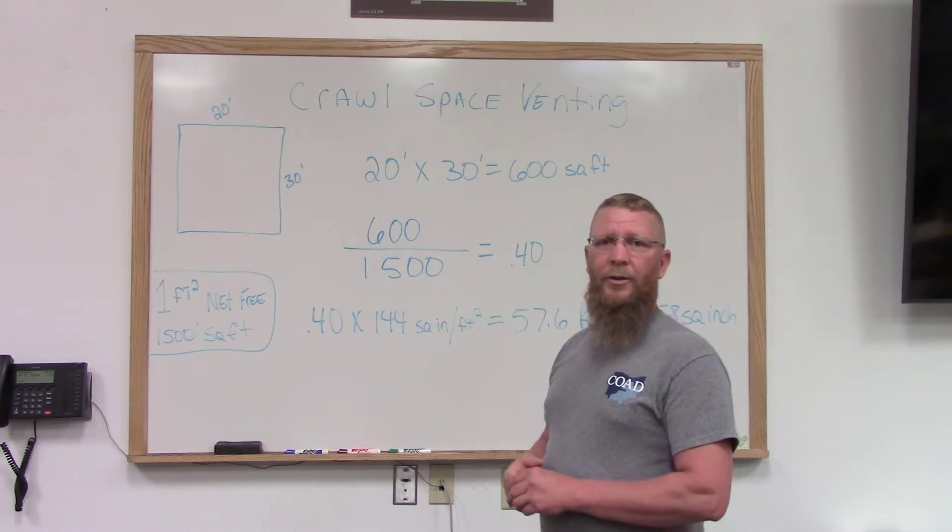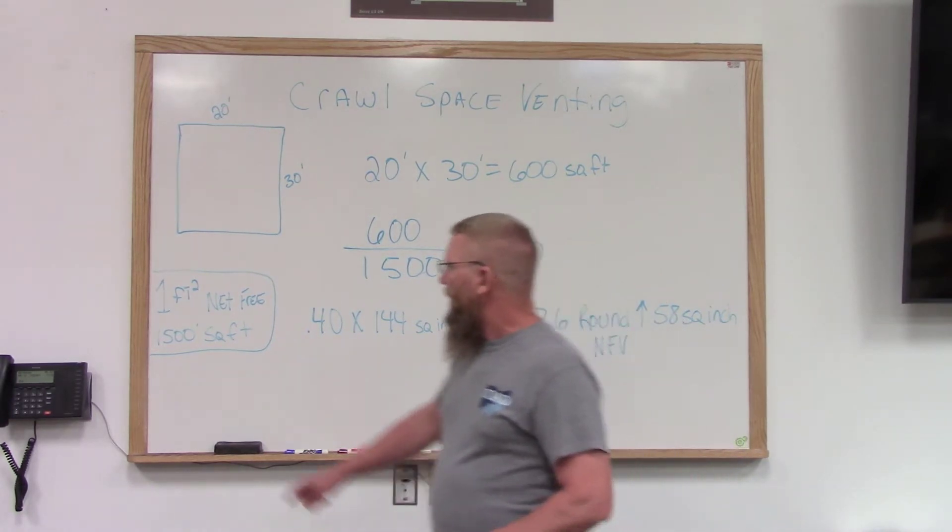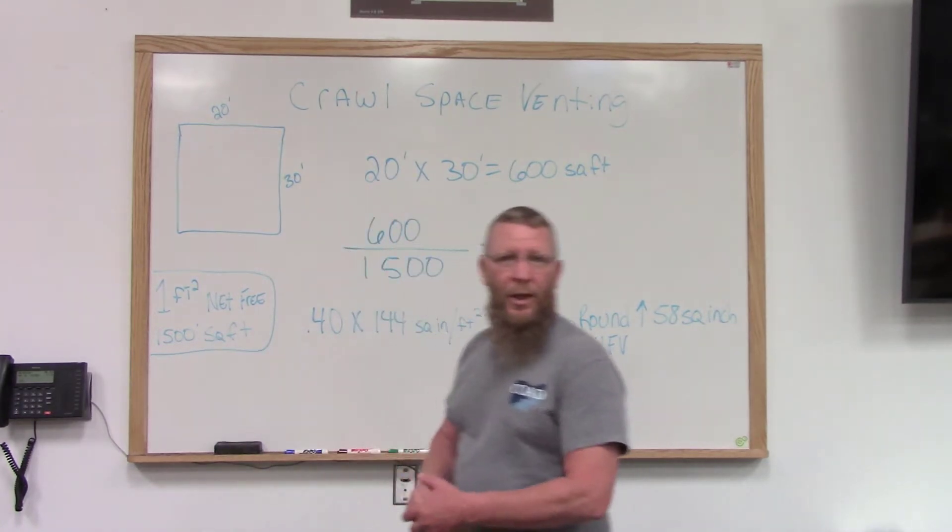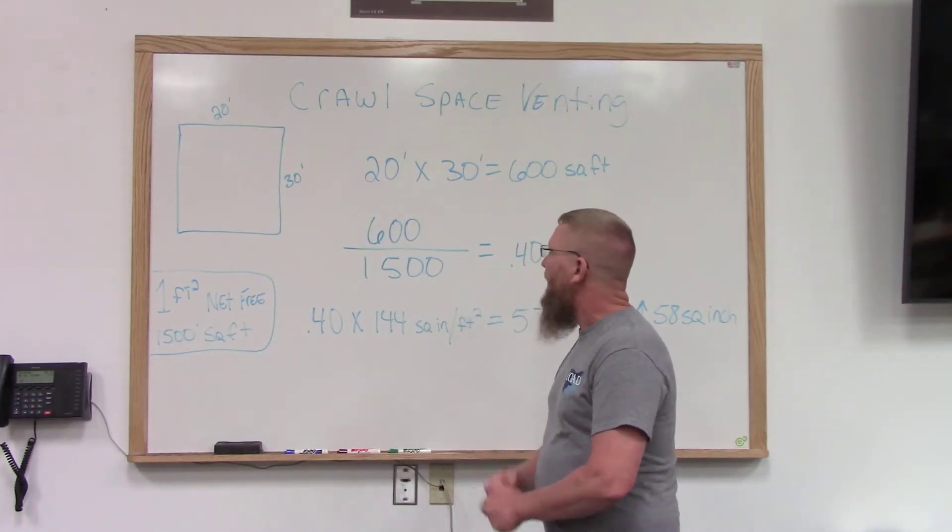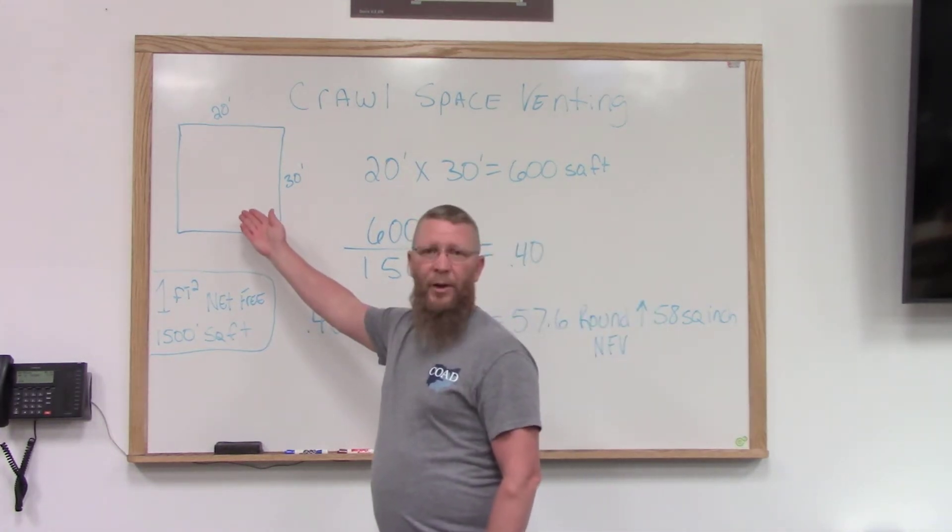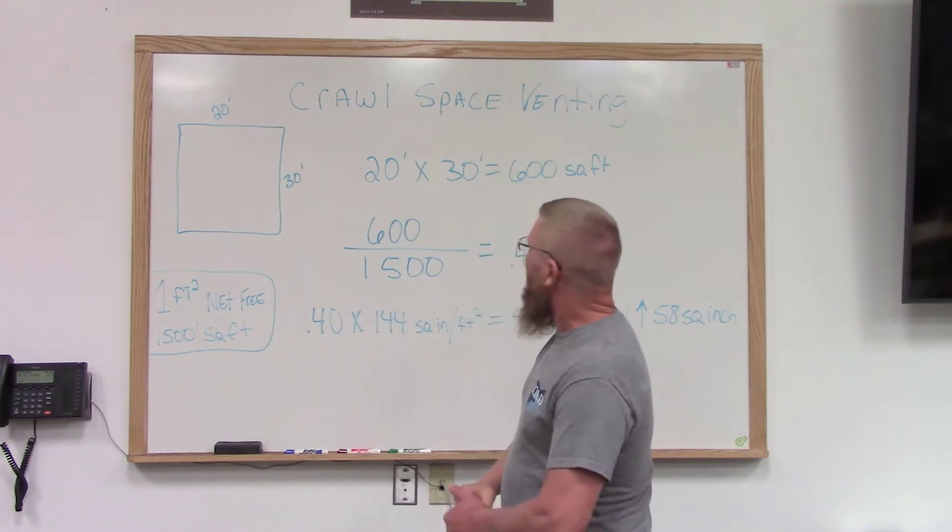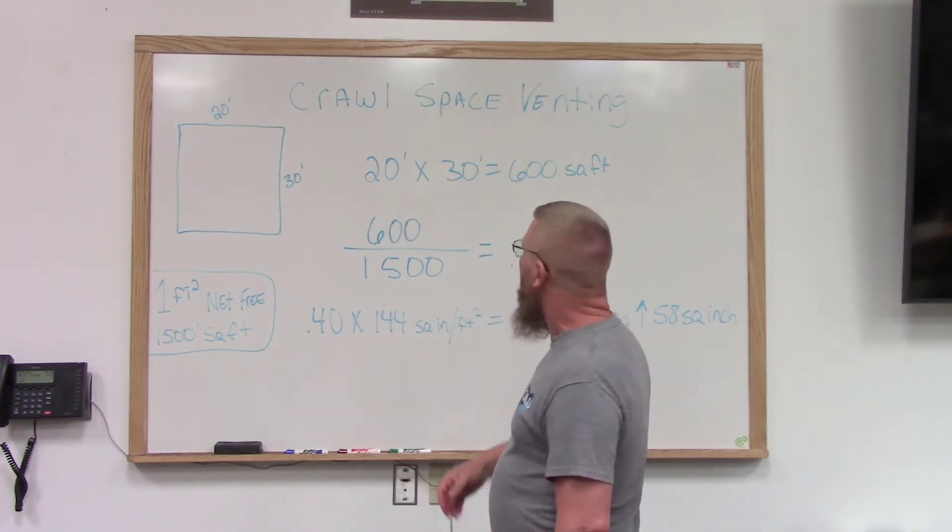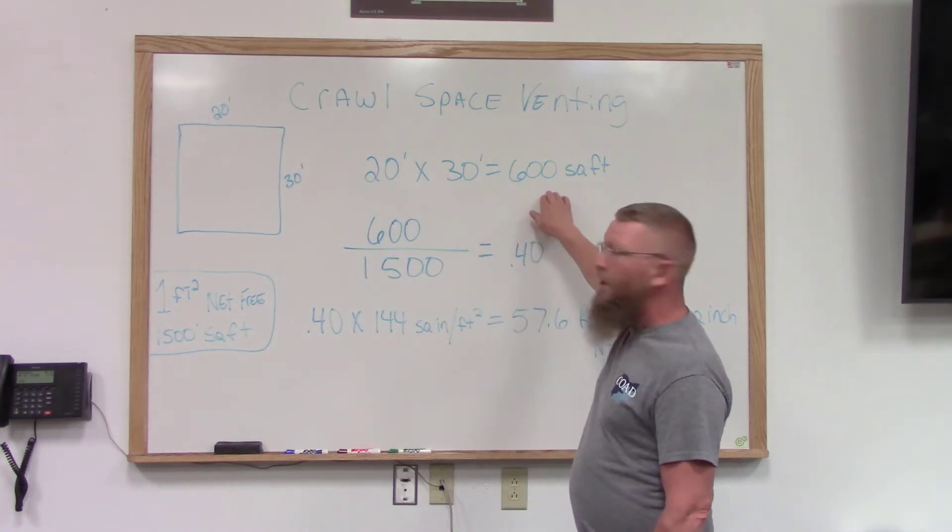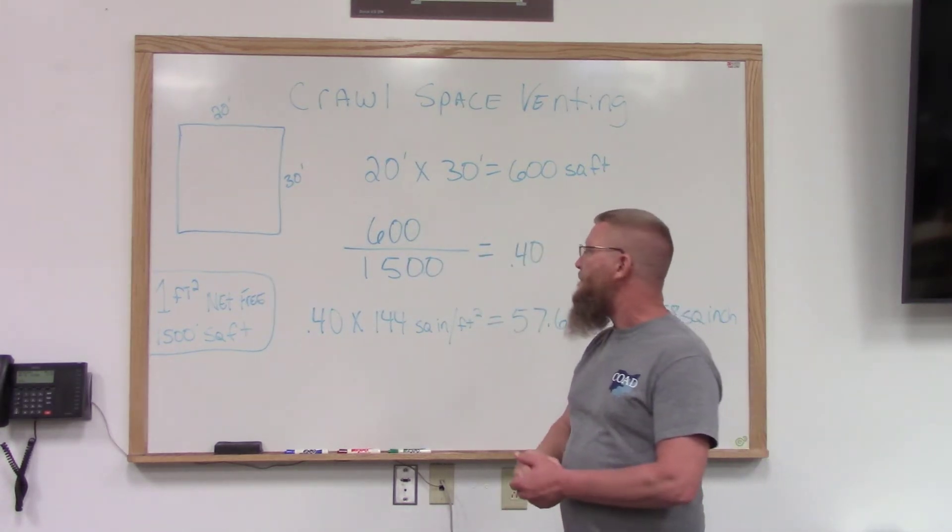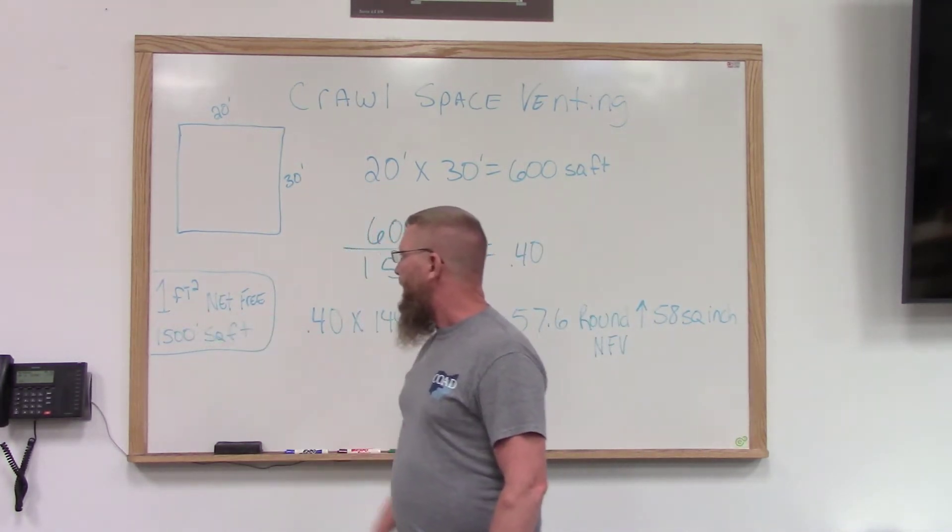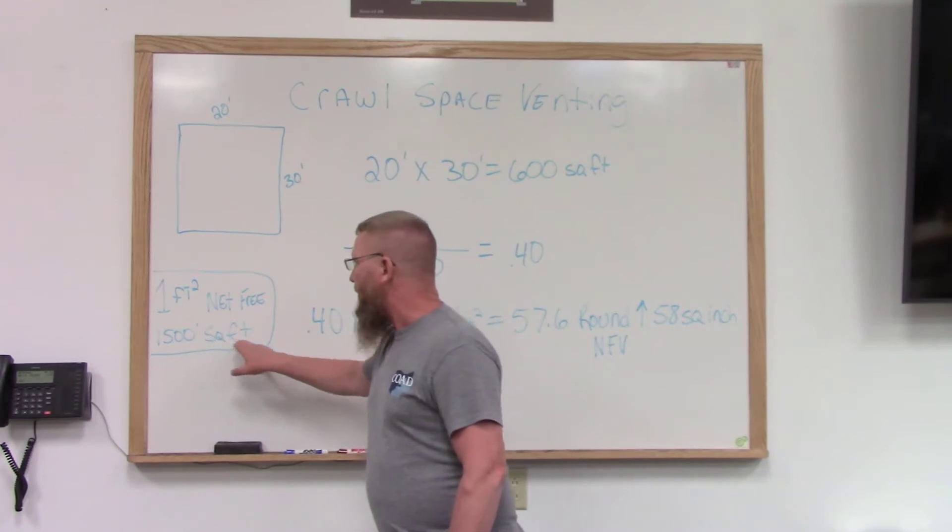The formula for figuring out crawl space ventilation is one square foot of net free venting for 1,500 square feet of crawl space. We're just going to use this as an example. I've got a crawl space that's 20 foot by 30 foot, so we'll try to find the area of that. And that comes up to 600 square feet. Well again, the formula, I need one square foot of net free venting for 1,500 square feet.